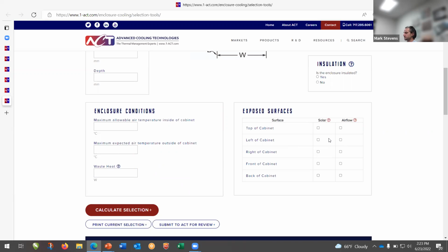The last selection you need to make is what surfaces may be exposed to sun and airflow. Some applications are completely indoor, in which case you'll select none of the solar options. Airflow refers to which faces of the cabinet are exposed to free-flowing air. If you have three cabinets stacked up next to each other, that middle cabinet will only have free surfaces on the front, maybe the back, and the top, so make sure you select those free surfaces applicably.